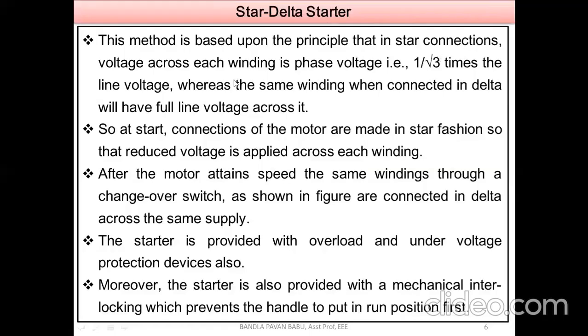So this method is based upon the principle that in star connections, the voltage across each winding is the phase voltage, that is 1 by root 3 times the line voltage, whereas the same winding when connected in delta will have the full line voltage across it. So this is the fundamental thing, the voltage equations in the star connection and the delta connection. So what is the line voltage there? In star it is 1 by root 3 times, whereas in delta it is root 3. Based upon that fundamental thing, we are going to regulate the speed. So let us see how it is.